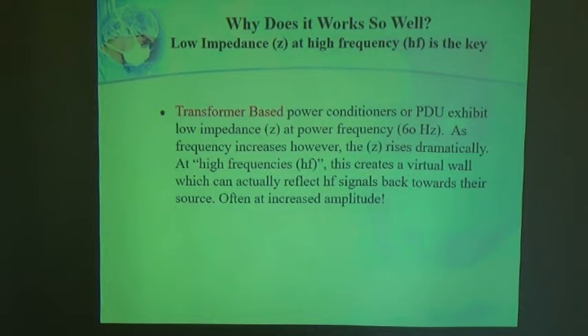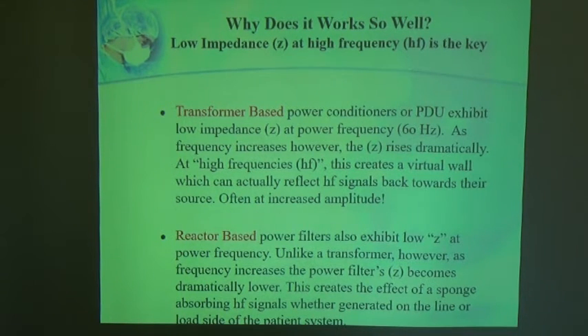Transformer-based power conditioners used in PDUs exhibit low impedance at power frequency, 60 Hertz. But as frequency increases, the impedance rises dramatically. And in fact, at high frequencies, this creates a virtual wall which can actually reflect those high frequency signals back towards their source, often at increased amplitude. Reactor-based power filters, on the other hand, also exhibit low impedance at power frequency. But unlike the transformer, as frequency increases, the power filter's impedance becomes dramatically lower. This creates the effect of a sponge, absorbing high-frequency signals, whether generated on the line or load side of the patient's system. Here's an example.